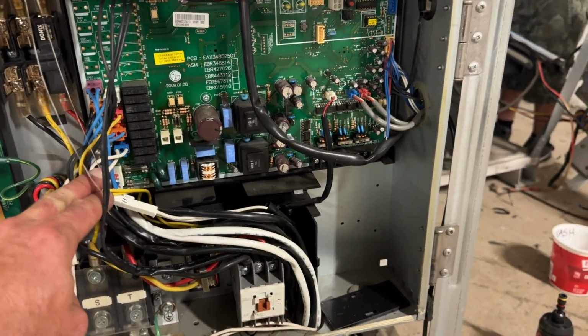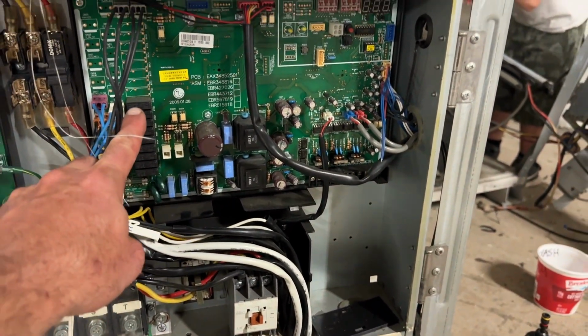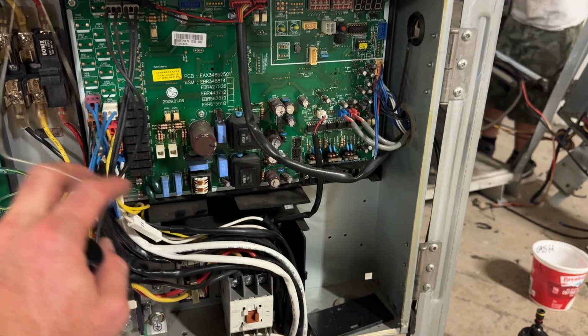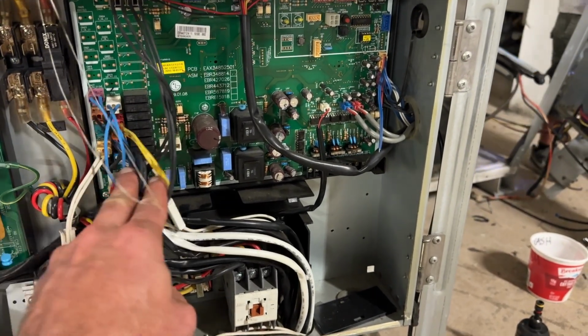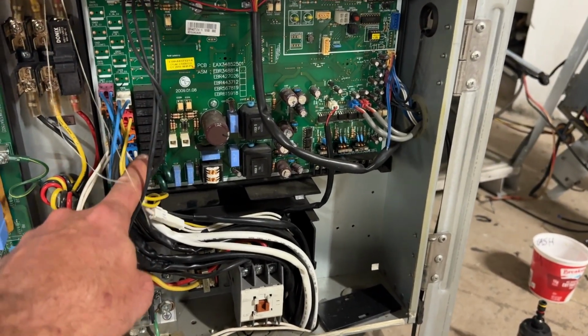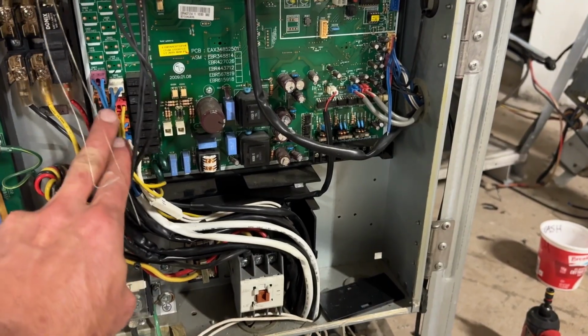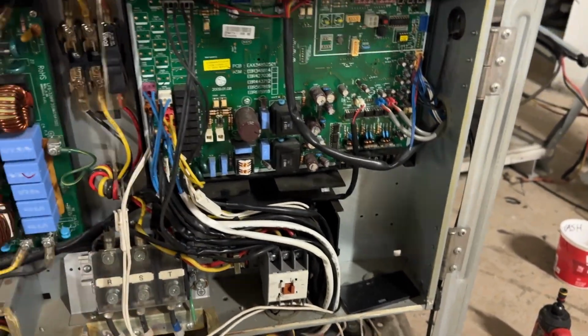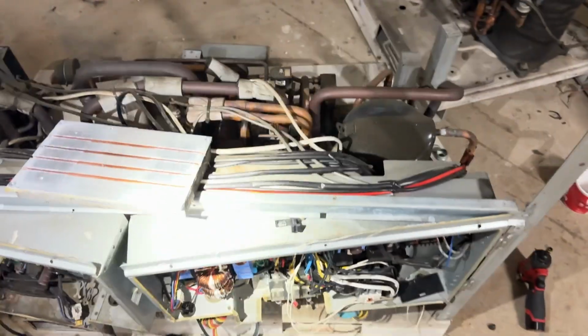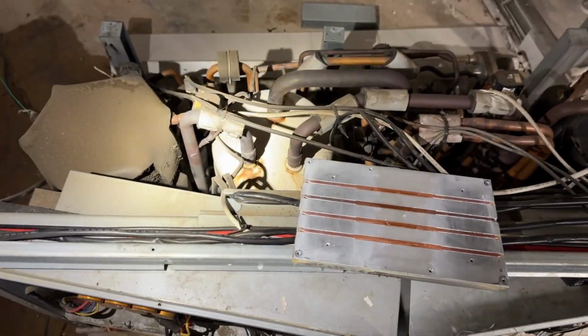Okay, there's a crankcase heater, and this is a pretty common design—you'll have a bank of relays all controlling these. So when you see these relays next to all these connectors, those are going to be your high voltage outputs, which on VRF units, your solenoids are always high voltage.